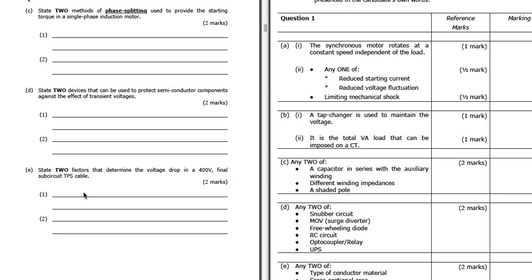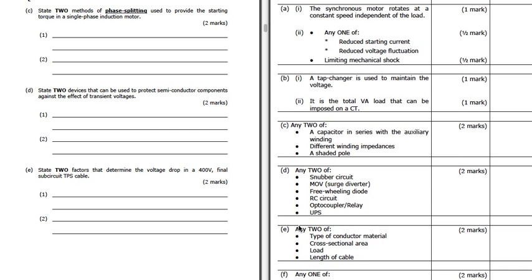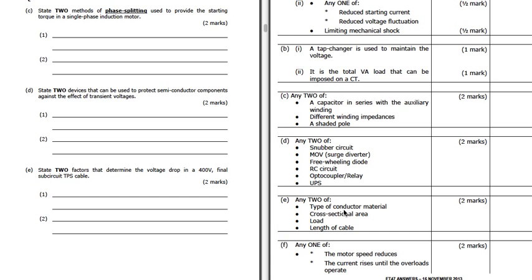State two factors that determine the volt drop in a 400 volt final sub-circuit TPS cable. So when we're looking at volt drop, what are we looking at? We're looking at the material, because that will give the resistance of the cable. Cross-sectional area, that will also affect the resistance. The load, which will be the current flowing through it, because V is I times R, so that's the I part. And length of cable, that's going to change the resistance as well. So these three are going to change the resistance of the conductor, and this is going to change the current.